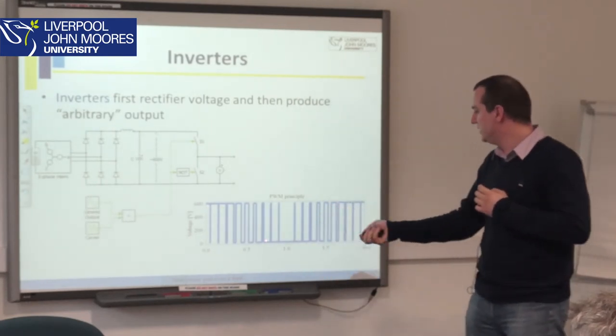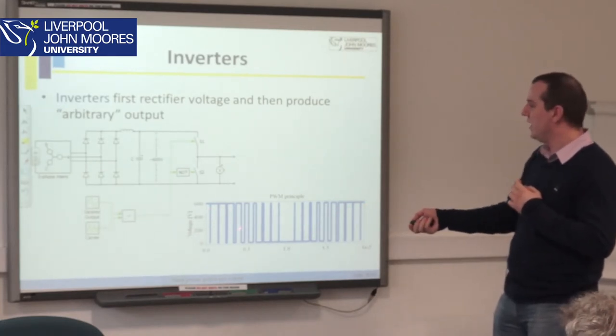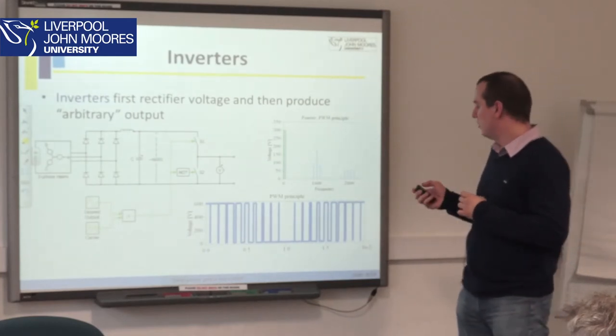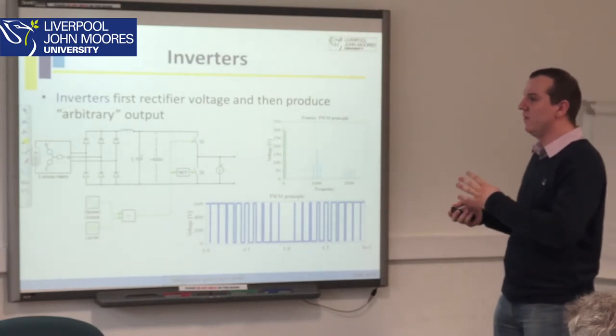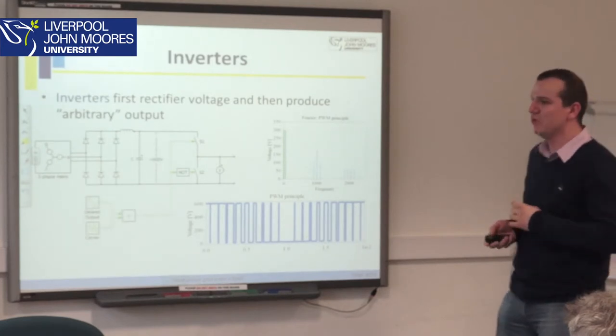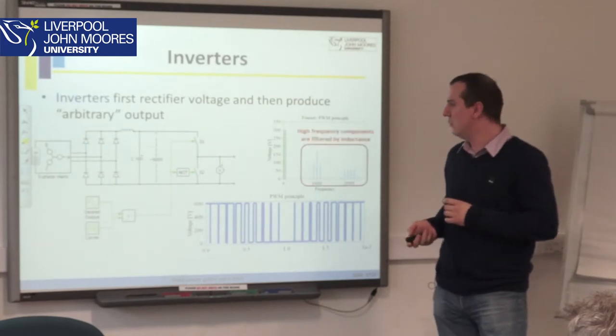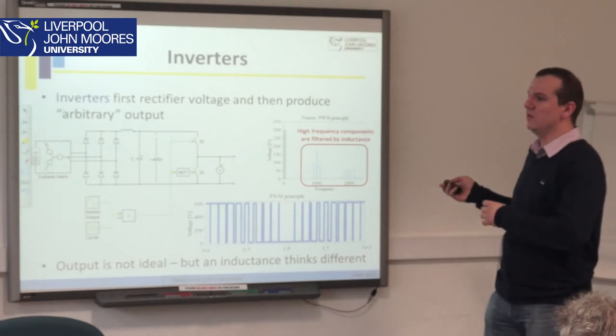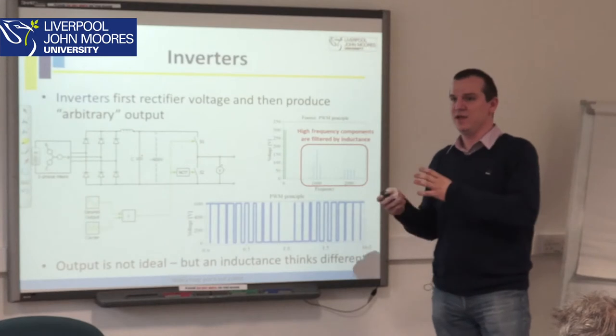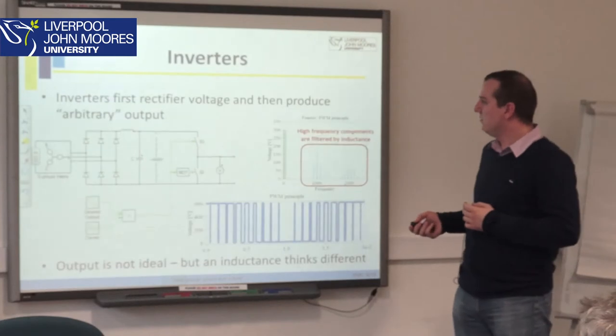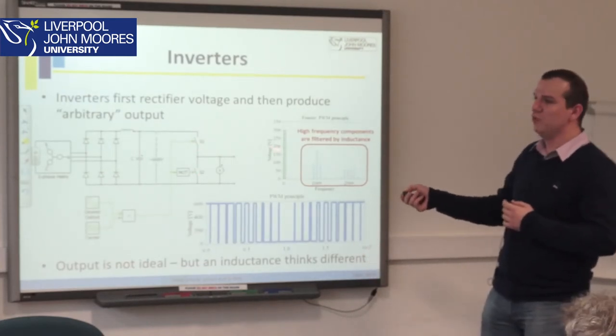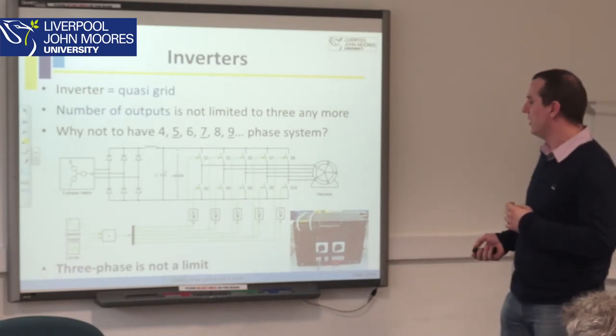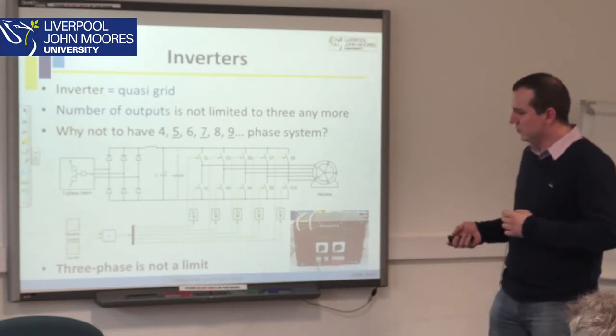The output voltage is not ideally sinusoidal, but on average the square-wave pattern is sinusoidal. Looking at the spectrum, we have the desired low-frequency component but also high-frequency components. However, inductance doesn't respond to those high frequencies, and all our machines have windings and inductance inside, so it is not a problem. I have shown only one phase here, but why not put more of them? Here is an example of a five-phase inverter, and here is what one of the inverters in our laboratory actually looks like. Three phases are not the limit.